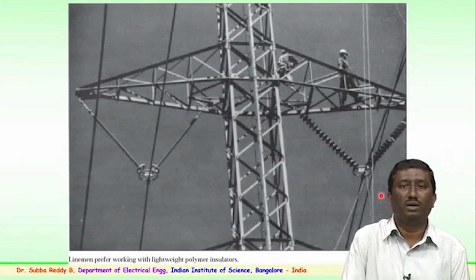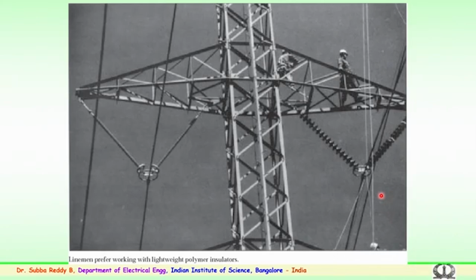So, I will compare the working of the engineers or technicians in the tower. Very clearly you can see, in the case of porcelain insulators for a 400 kV system, with the hardware the material weight is very high. This shows the polymer insulators with lesser hardware and fewer corona control rings. So, people like to work in this area in comparison to this area. So the technology has improved, and a lot of new types of polymer insulators are being used for EHV and ultra high voltage transmission systems.